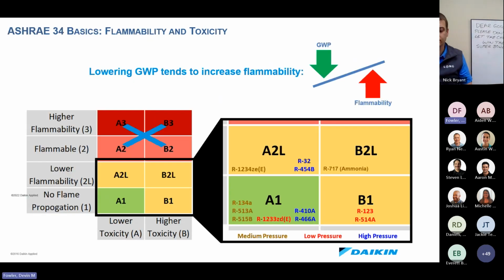Some things to talk about before we get into the discussion on refrigerants. ASHRAE 34 classifies our refrigerants, what most of the industry uses, as either A1, A2L, or B1 refrigerants. What this means is that A1, you're going to have no flame propagation and a lower toxicity. A2L will have low flammability with a low toxicity, and then B1 refrigerants are going to be no flame propagation with a higher toxicity. The current industry standards in the United States are R134A and R410A.